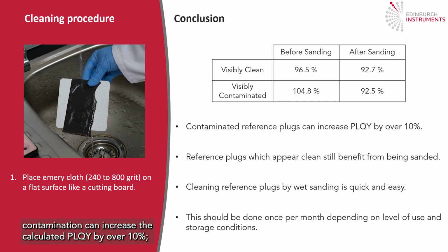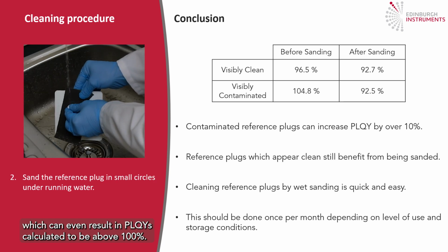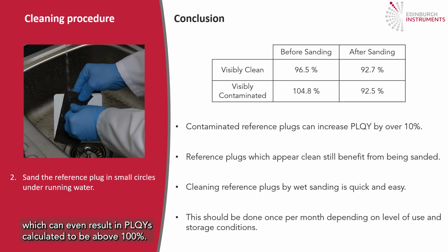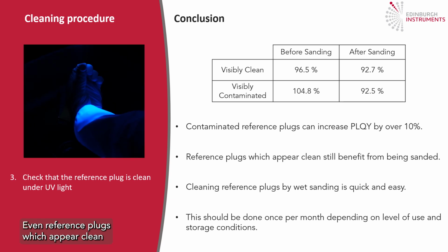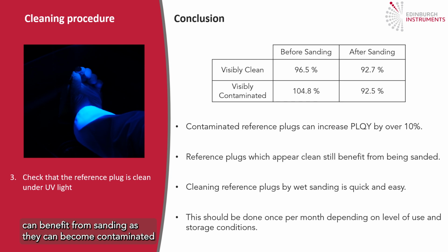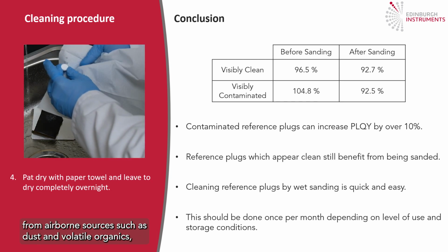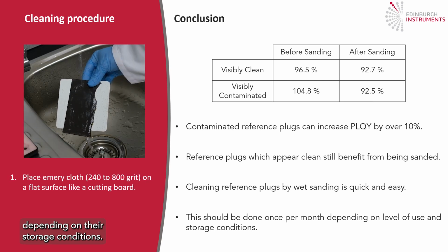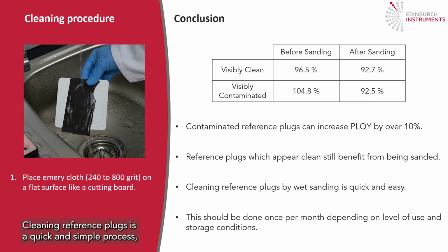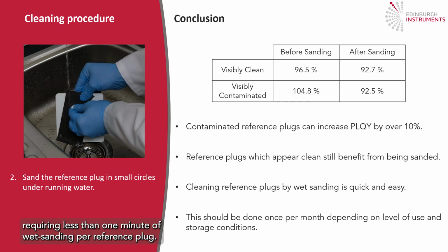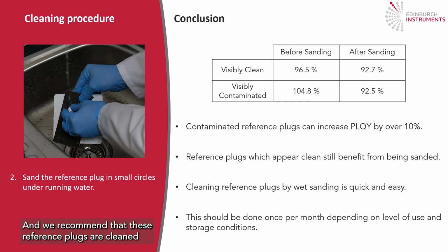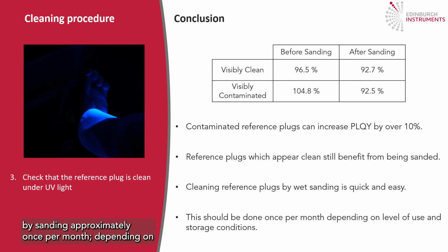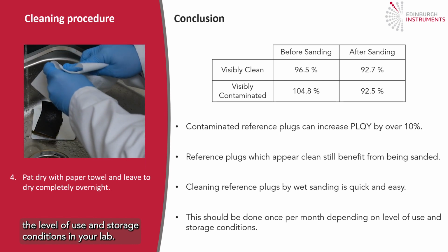So to conclude, contamination can increase the calculated PLQY by over 10%, which can even result in PLQYs calculated to be above 100%. Even reference plugs which appear clean can benefit from sanding, as they can become contaminated from airborne sources such as dust and volatile organics, depending on their storage conditions. Cleaning reference plugs is a quick and simple process requiring less than 1 minute of wet sanding per reference plug, and we recommend that these reference plugs are cleaned by sanding approximately once per month, depending on the level of use and storage conditions in your lab.